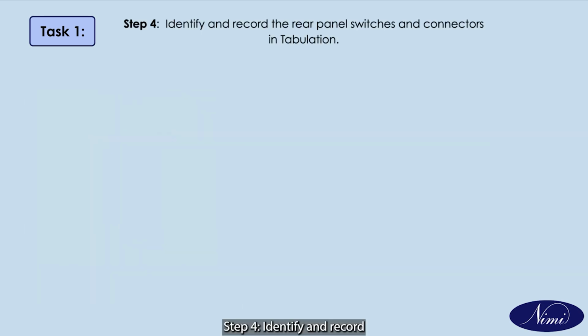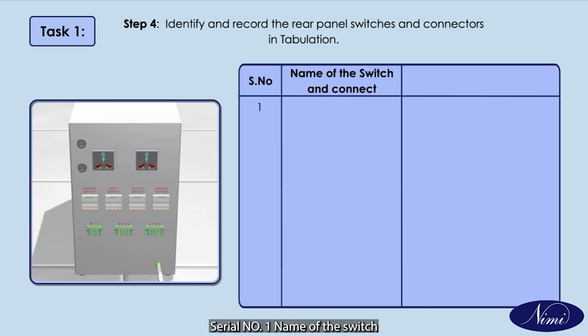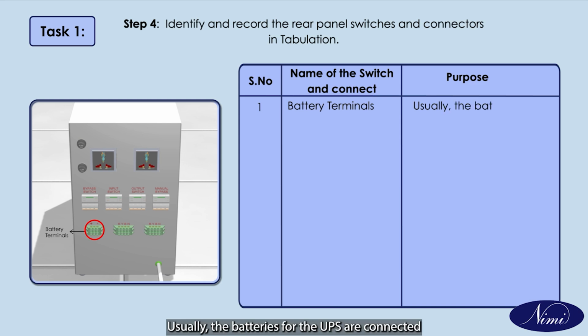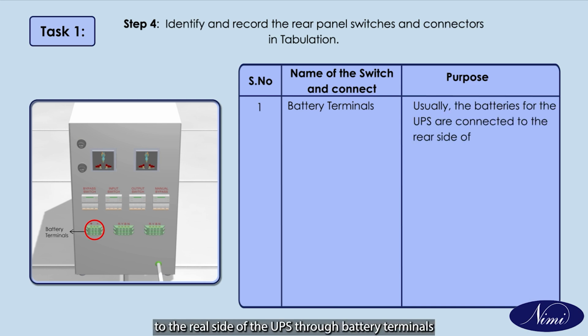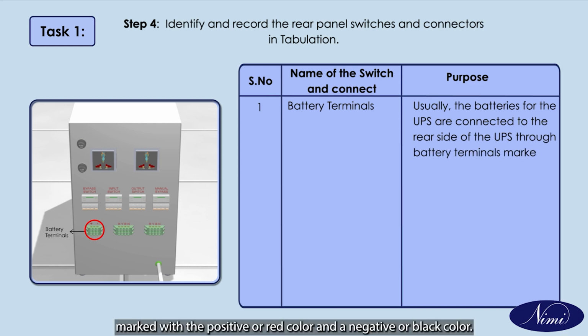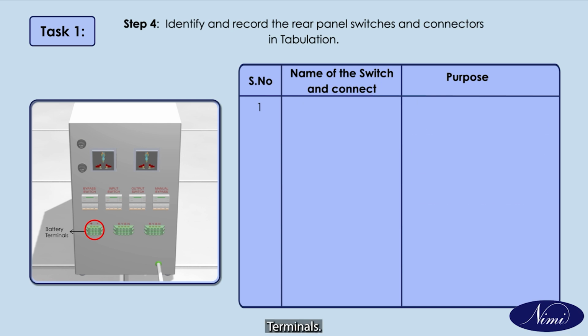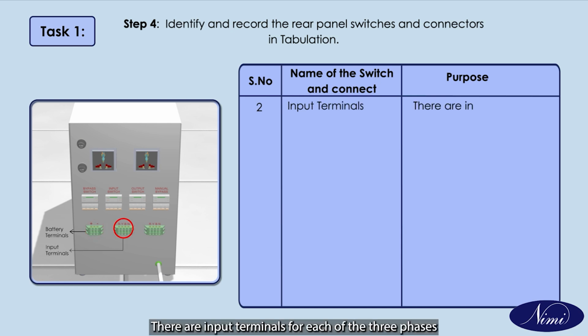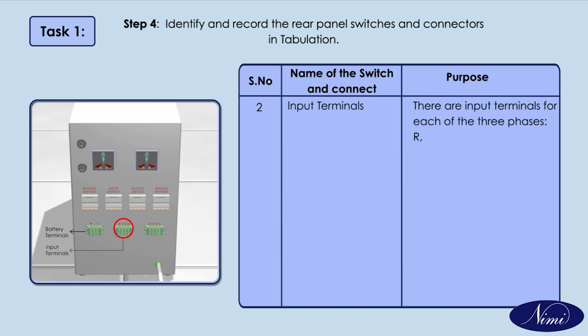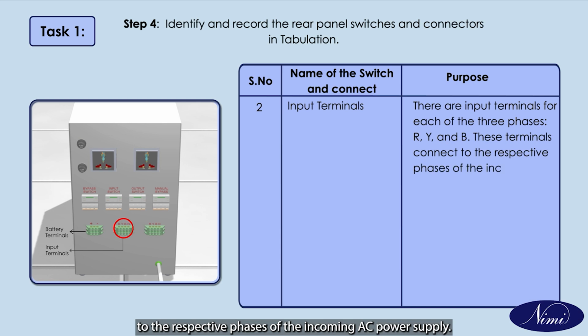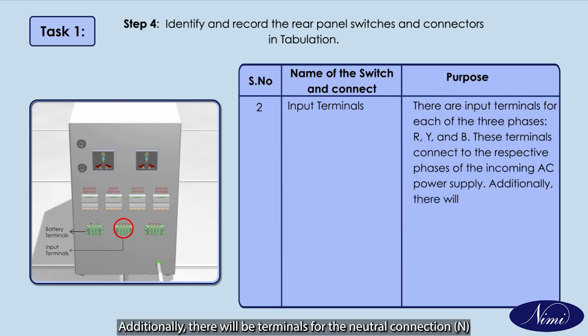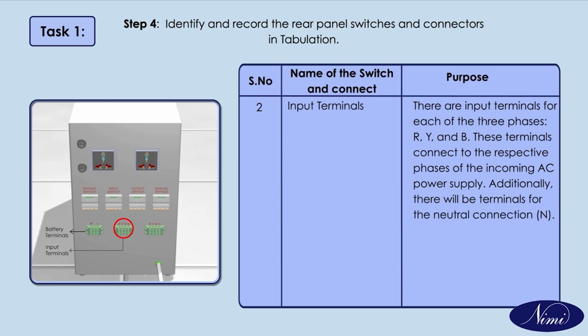Step 4. Identify and record the rear panel switches and connectors in tabulation. Serial number 1. Name of the switch and connector: battery terminals. Purpose: usually the batteries for the UPS are connected to the rear side of the UPS through battery terminals marked with a positive or red color and a negative or black color terminals. Number 2. Input terminals. There are input terminals for each of the three phases R, Y and B. These terminals connect to the respective phases of the incoming AC power supply. Additionally, there will be terminals for the neutral connection N.